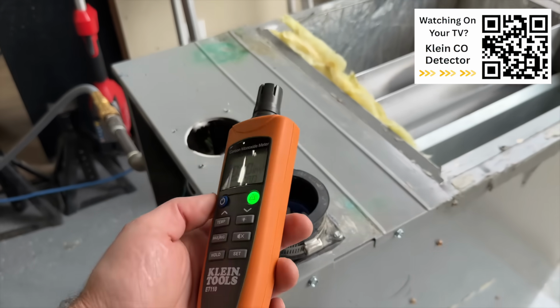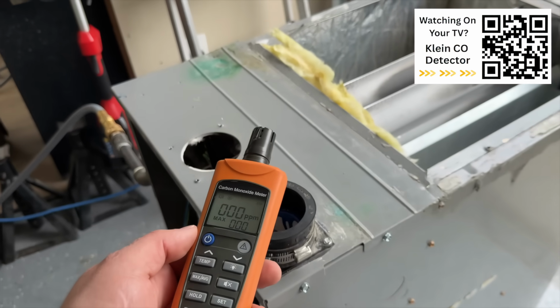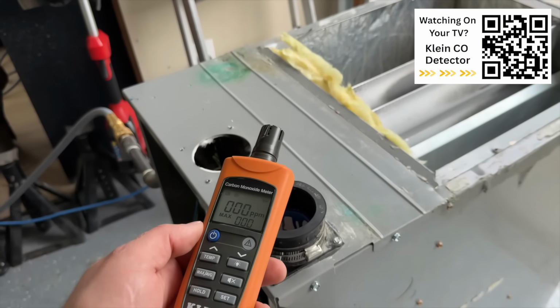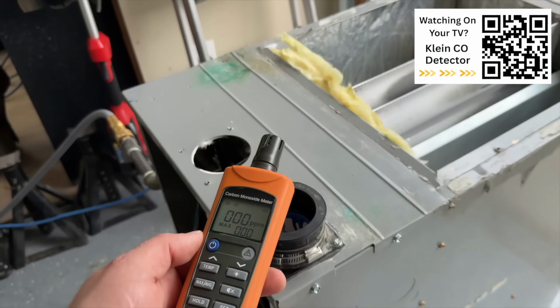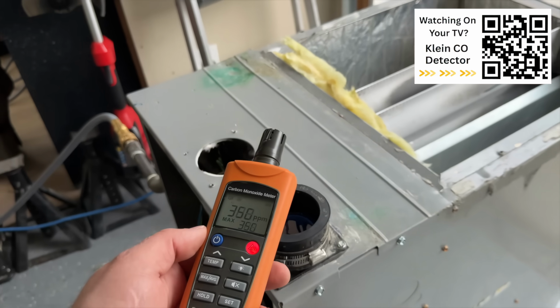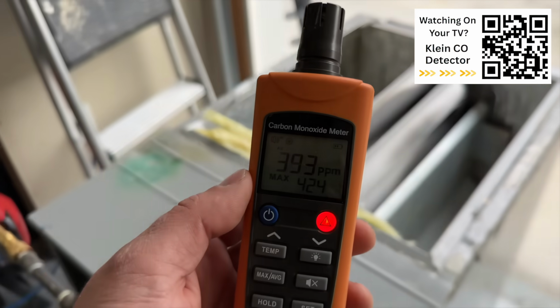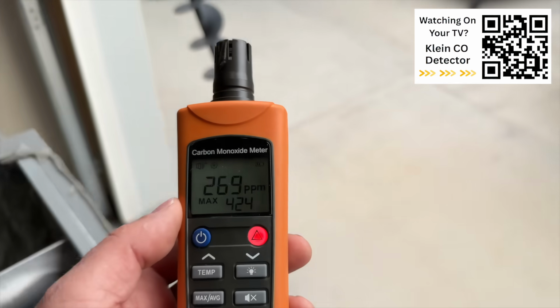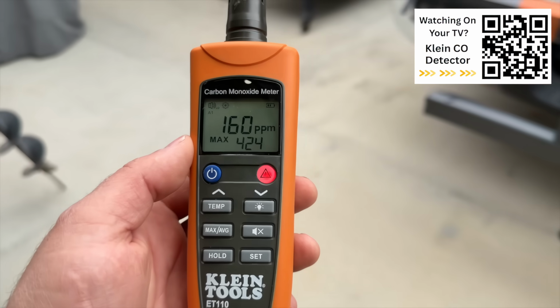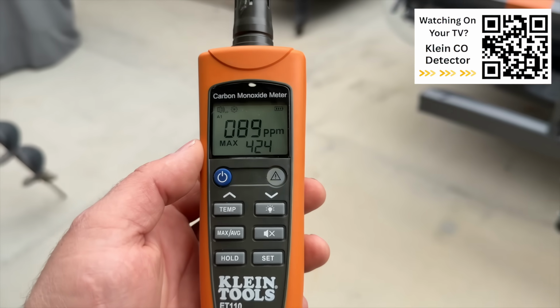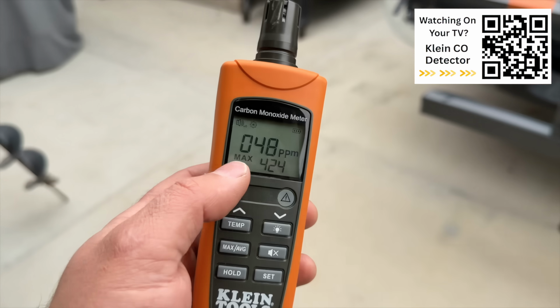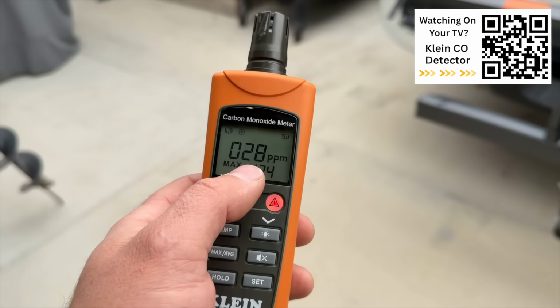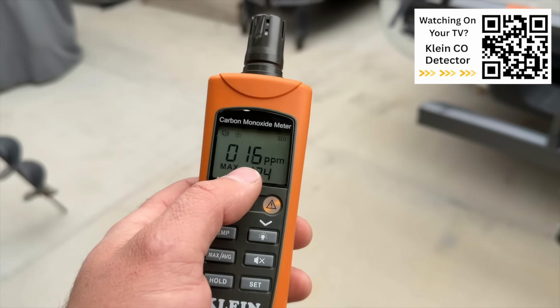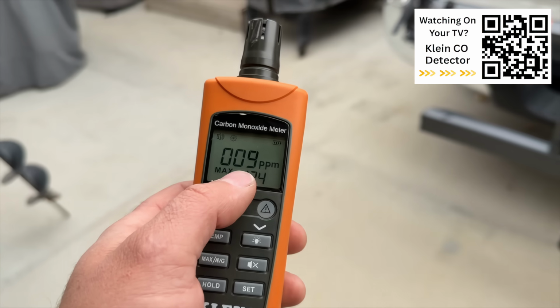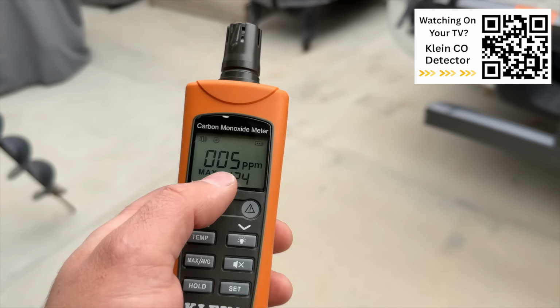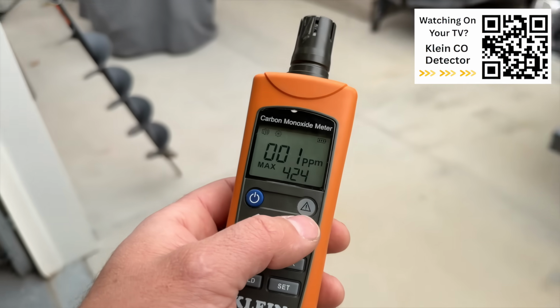This, again, is the tube that would go outside to the exterior of your home. And notice, as soon as our flames come on, boom, we have 450 parts per million. So this will alert you, and as soon as you get away from it, it will slowly beep until we get down to a safe level. So even anything above 9 parts per million, you're going to get a yellow flash here.